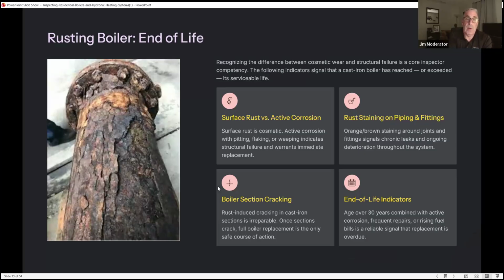So we're going to see rusting. Recognizing the difference between cosmetic wear and structural failure is a core inspector competency. The following indicators signal that a cast iron boiler has reached or exceeded its serviceable life. So you need to know the difference between surface rust and active corrosion. Surface rust is cosmetic. Active corrosion with pitting, flaking, or weeping indicates structural failure and warrants immediate replacement.